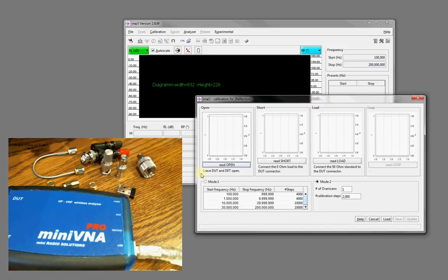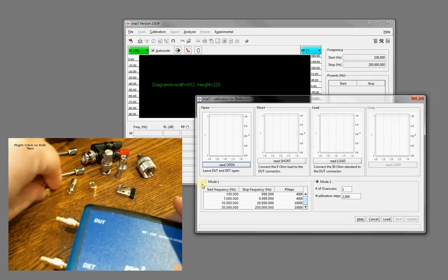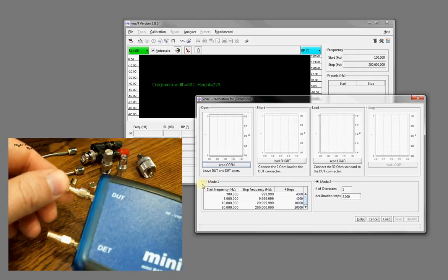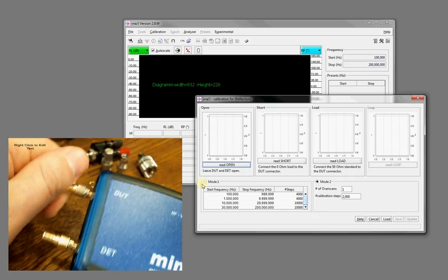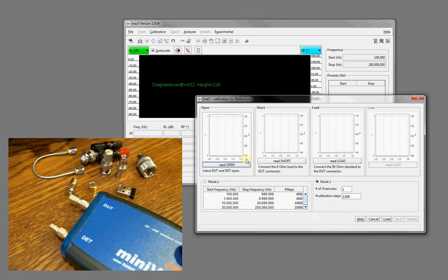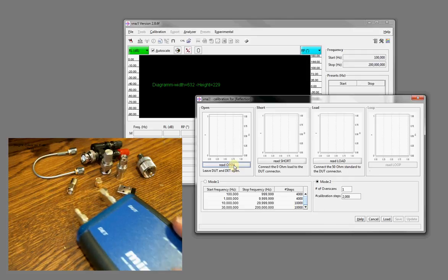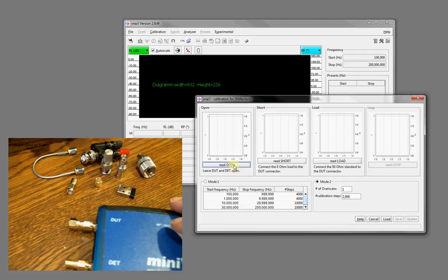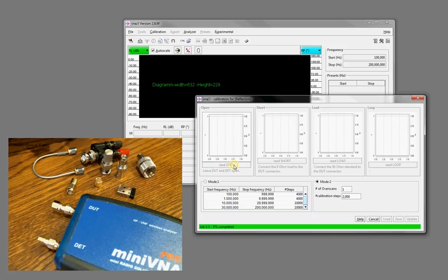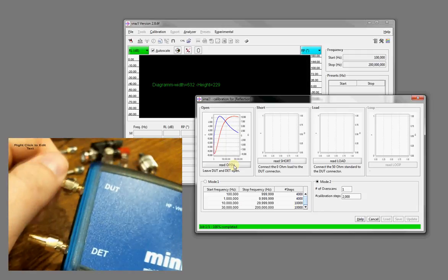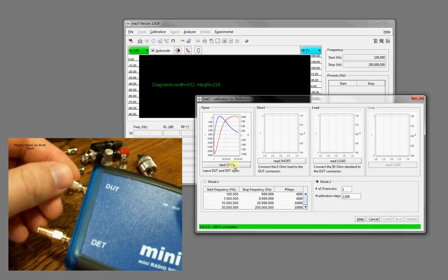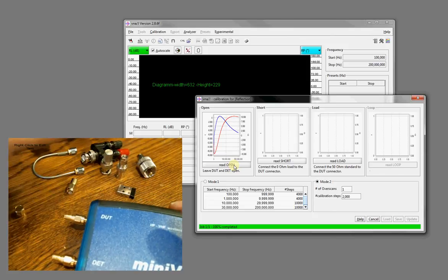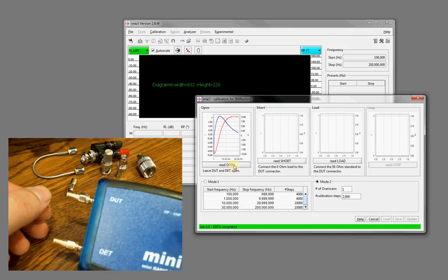It says leave the DUT and DET port open. But I got this open calibration stuff here, so we're going to screw it to the DUT port. There we go. And we're going to read it. All right, let's stop it from sliding off my table here. I have it in a weird position. So let's do that. Takes a couple seconds. There we go. That sort of looks like how the graph shows in the manual. If you see something different from that, there might be either an issue with RF getting in, or there might be an issue with the box itself, but I haven't had that problem yet.